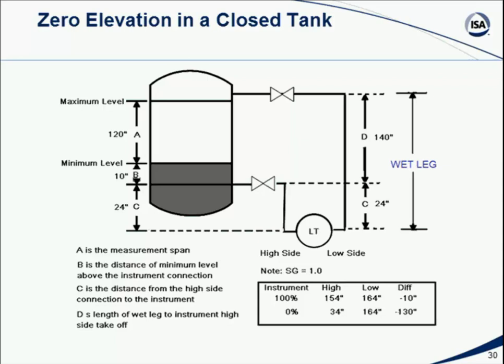But the problem with dry legs is they don't stay dry. Typically in a pressurized tank like this, the vapor above the fluid quite often is some type of condensing liquid. For example, let's just assume the tank has water. It's a boiler, right? So what's above the fluid level is steam. Well, that means that steam is going out through that tap up top into the leg, and what happens with steam? If we put steam into that leg, eventually it cools down, and what happens?